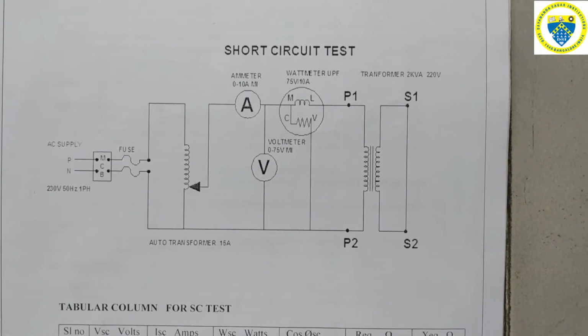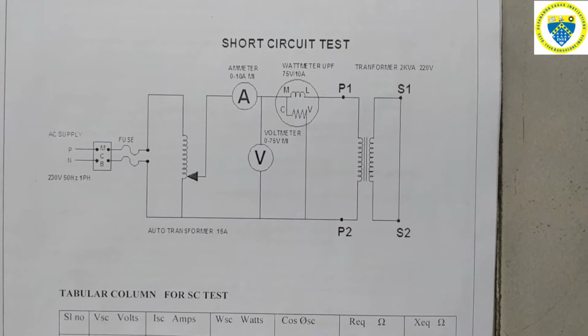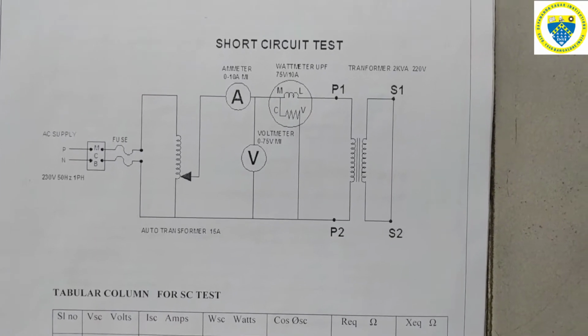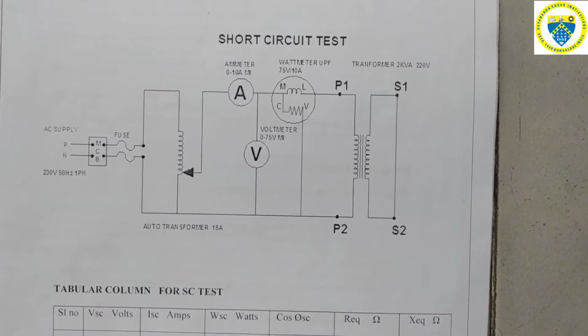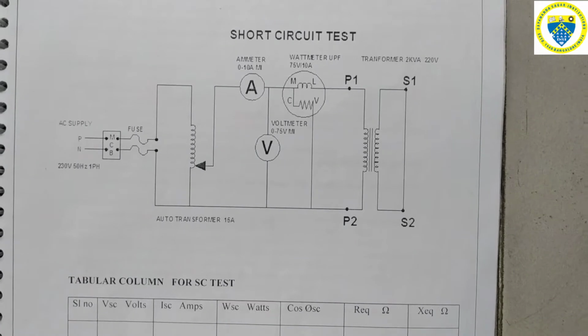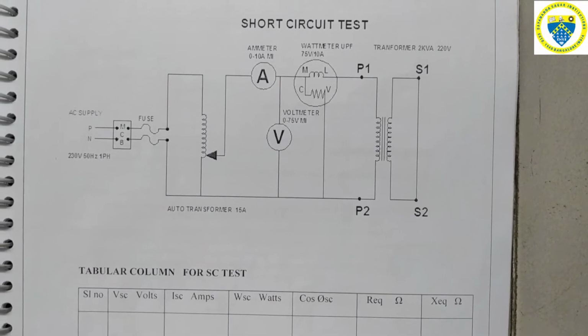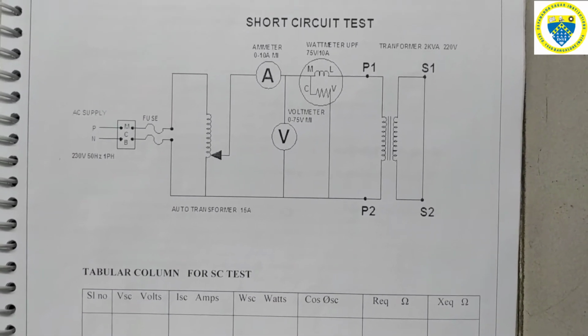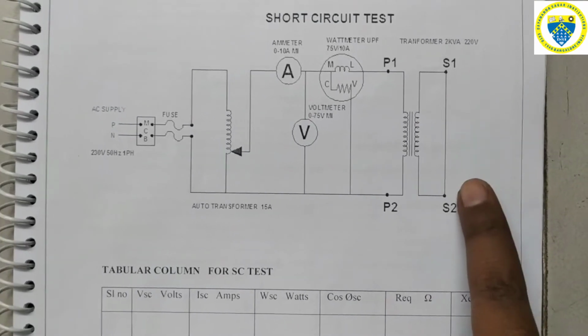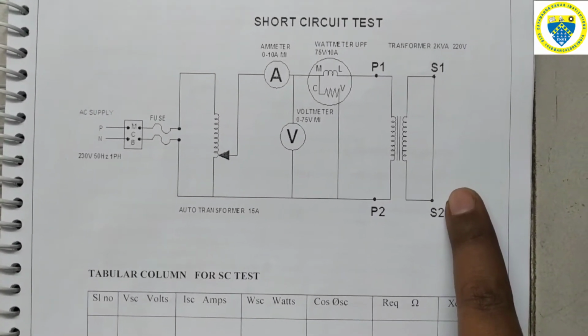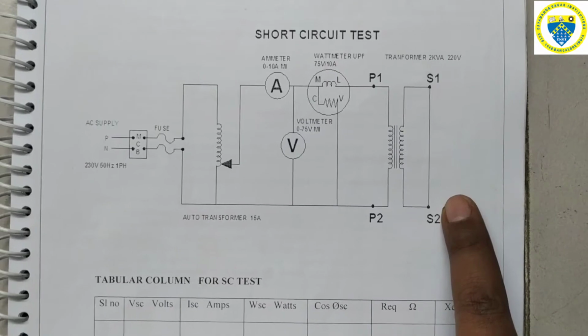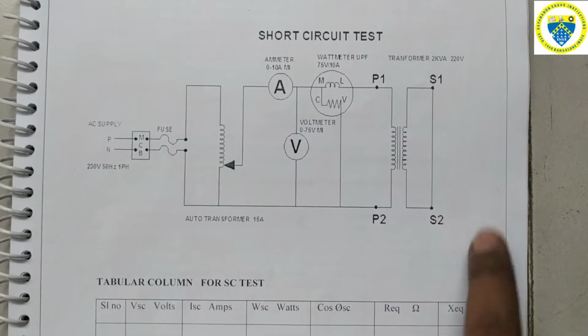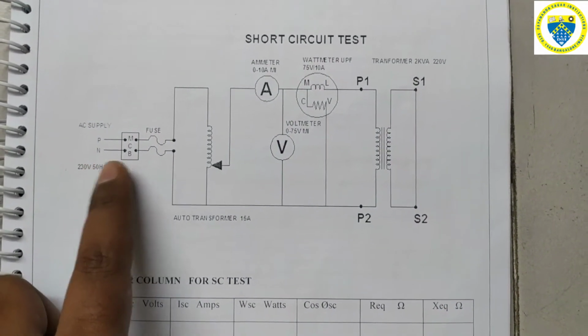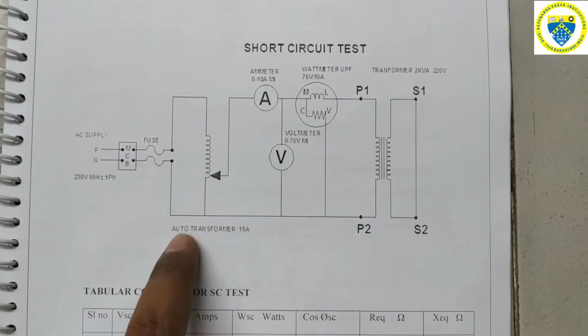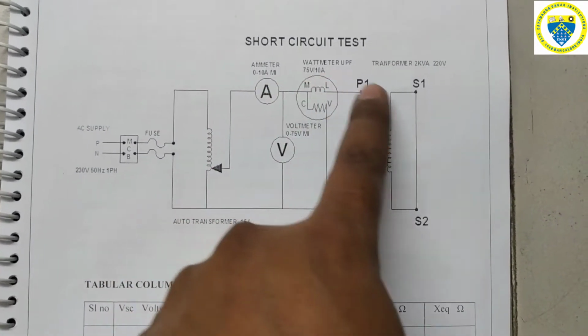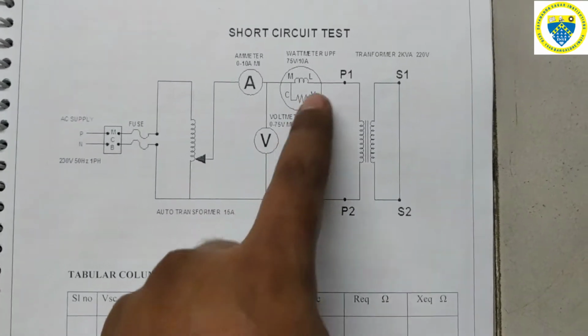Hello everyone. Now we'll see how exactly the short circuit test will be conducted on a single phase transformer. The circuit diagram is similar to the open circuit test, the same thing holds good, except that the secondaries are short circuited, because we are conducting a short circuit test on a single phase transformer. Here also we are using a mains along with the MCB, then we'll be using an auto transformer. Again the series connection will be done first, then we'll be doing the parallel connections.